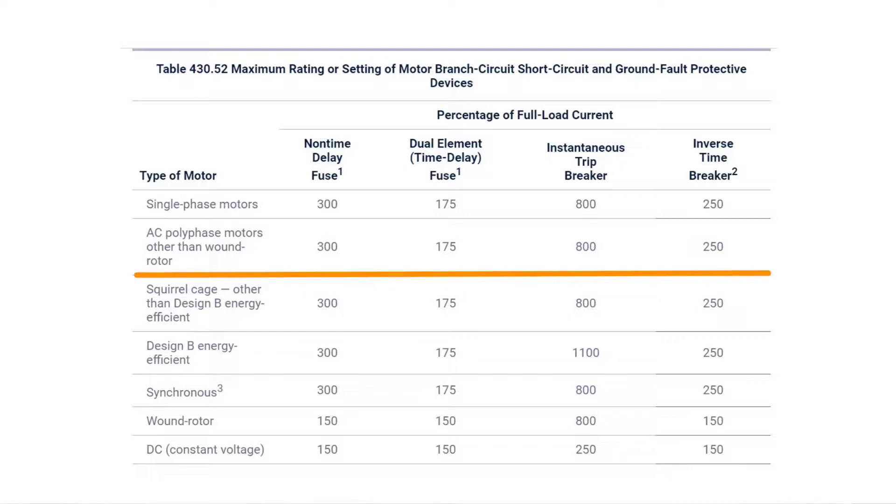We've got a non-time delay fuse selection, and we've got 300% and 300%. I want you to take your dark color highlighter and just make a fence post to segregate each side of that non-time delay fuse. Then we've got the dual element time delay fuse, put another fence post in. We've got the instantaneous trip circuit breaker, another fence post. We've got the inverse time circuit breaker, another fence post. Now we can just pick a box. Rather than look at this whole table, just pick a box.